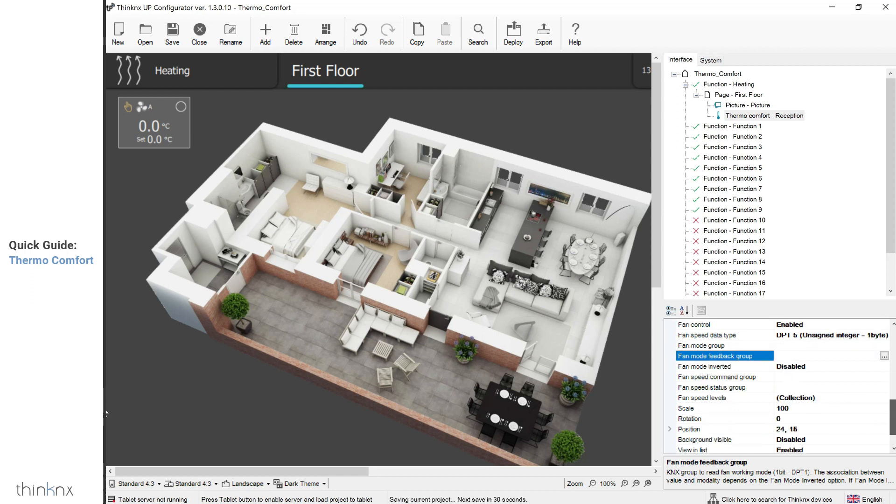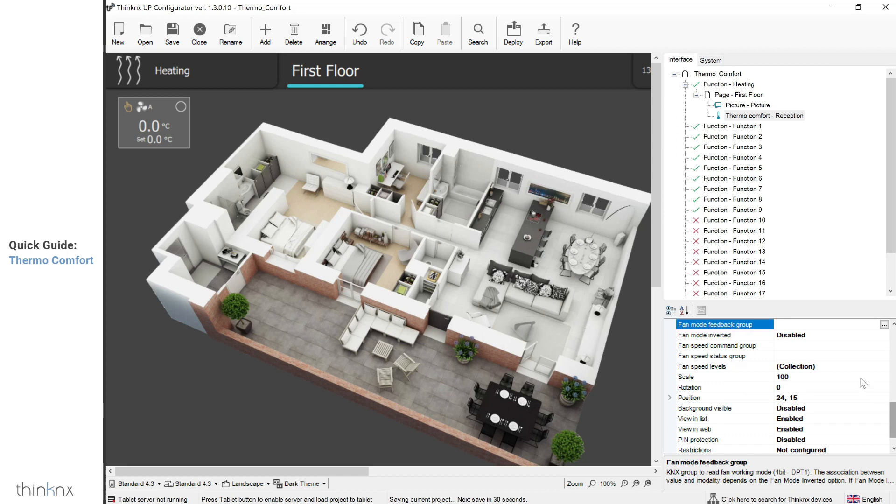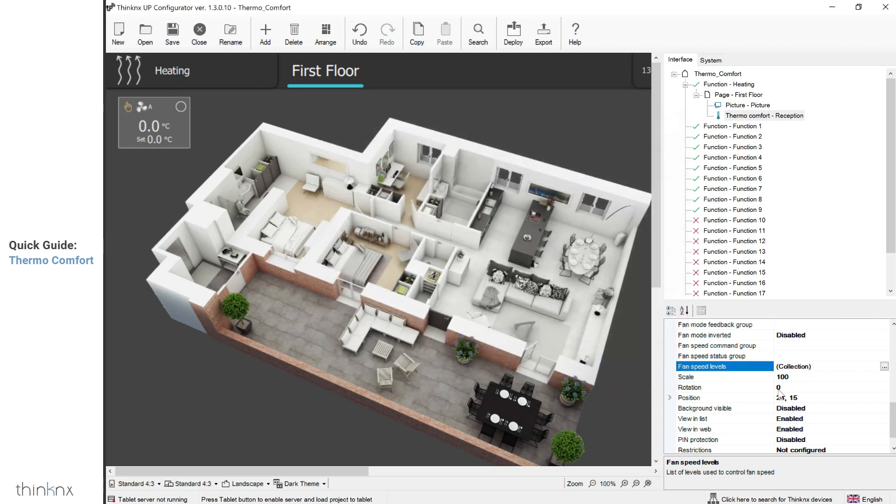Next, enter the fan speed command 1-byte group and the corresponding 1-byte feedback. You can configure your fan speed levels by accessing the collection and editing each fan speed. You can also add or remove speeds according to your site condition.